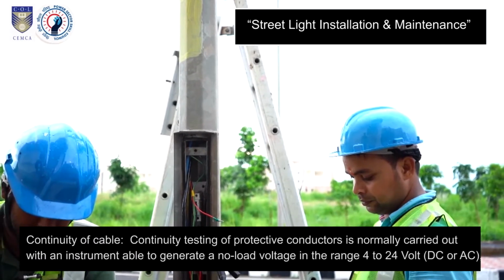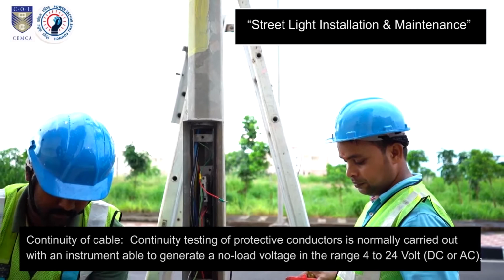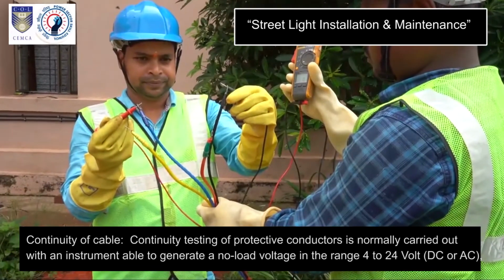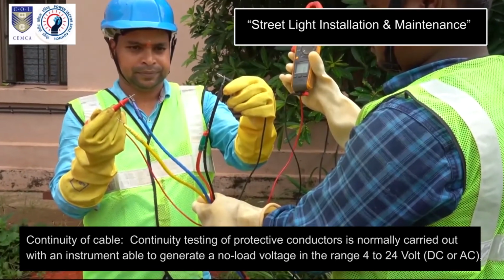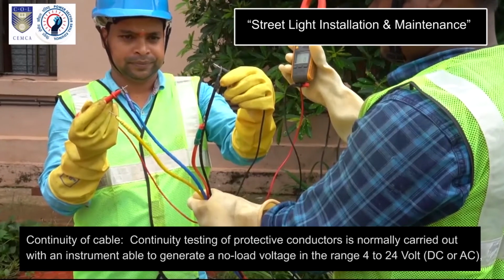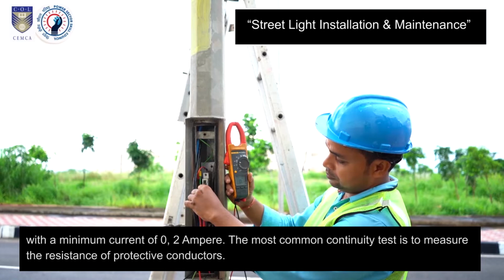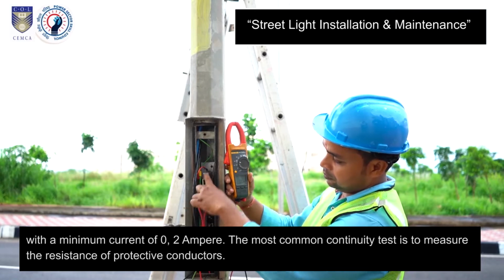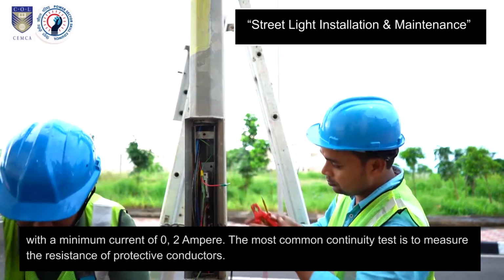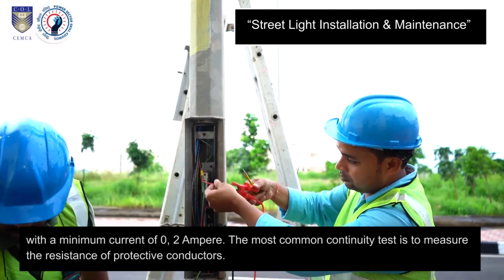Continuity of cable. Continuity testing of protective conductors is normally carried out with an instrument able to generate a no-load voltage in the range 4 to 24 volt DC or AC with a minimum current of 0.2 ampere. The most common continuity test is to measure the resistance of protective conductors.